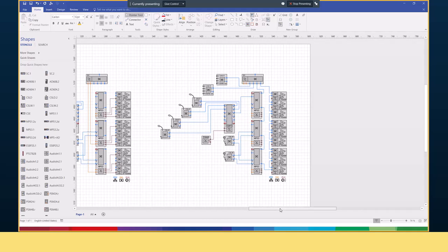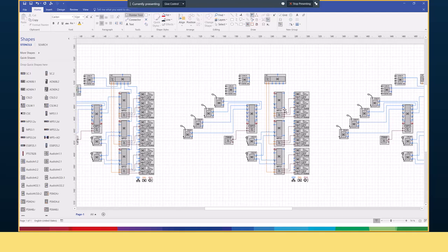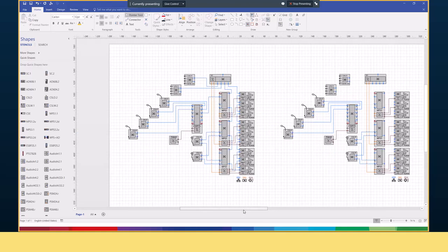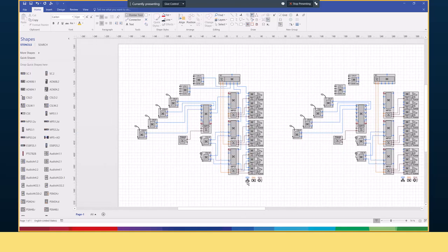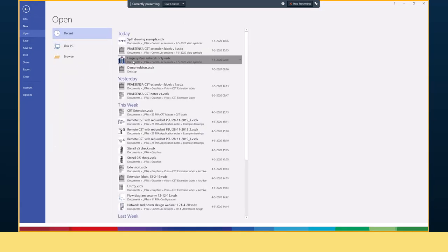Yeah, so a network diagram, a power diagram. Nice thing about the power diagram is that you see that you have enough power, that you have enough power connections. And this is the diagram where we have everything in one diagram. Also here in the lower part of this, you see the explanation for the different colors. Yeah, lifeline and power, power and network cable. There's no glass fiber in this example. I have another example that is an example of a really big system, and that is this one.